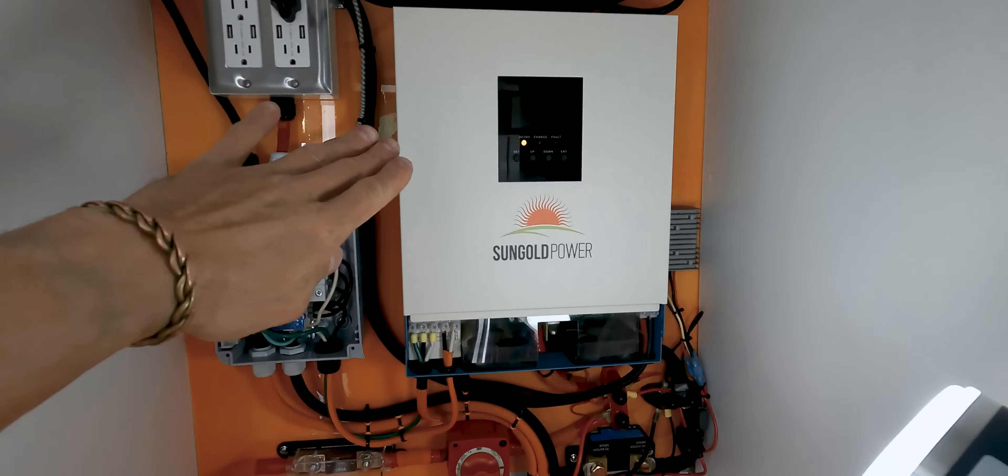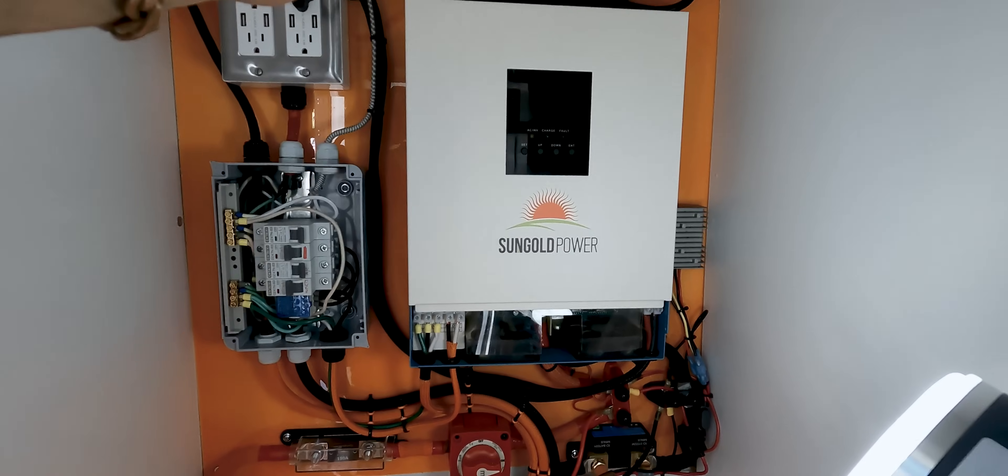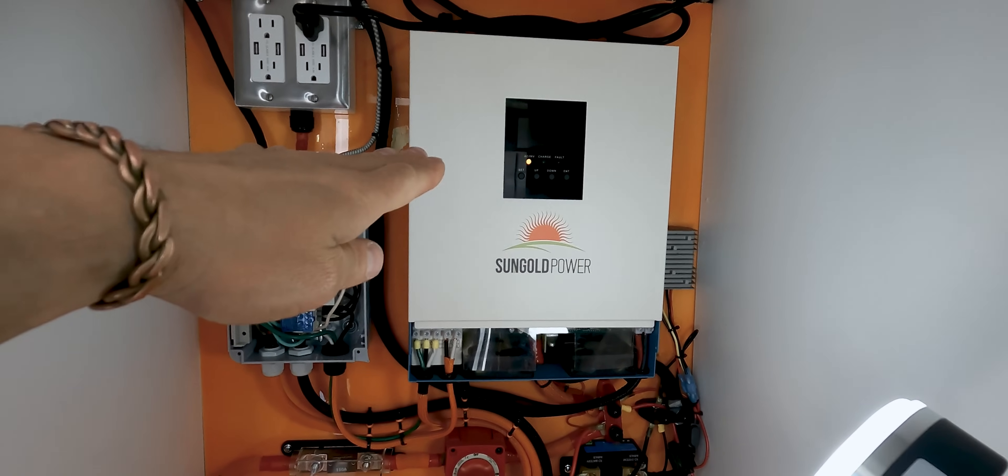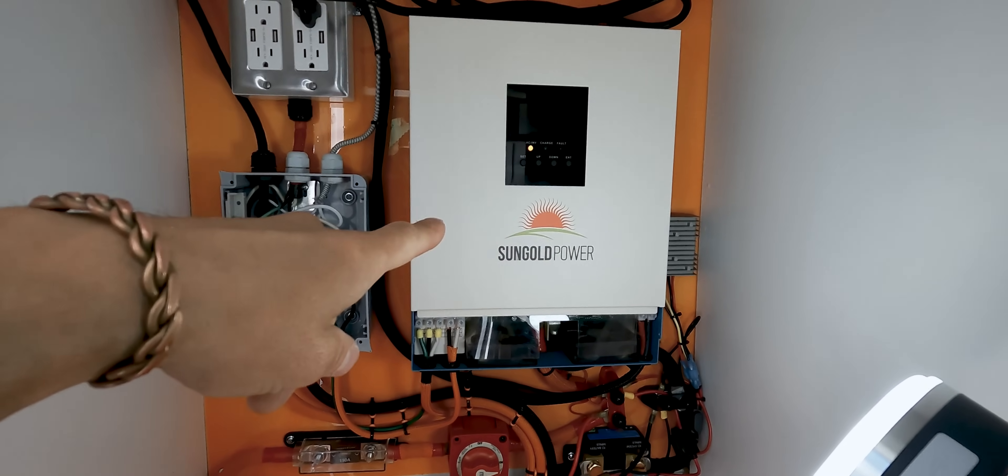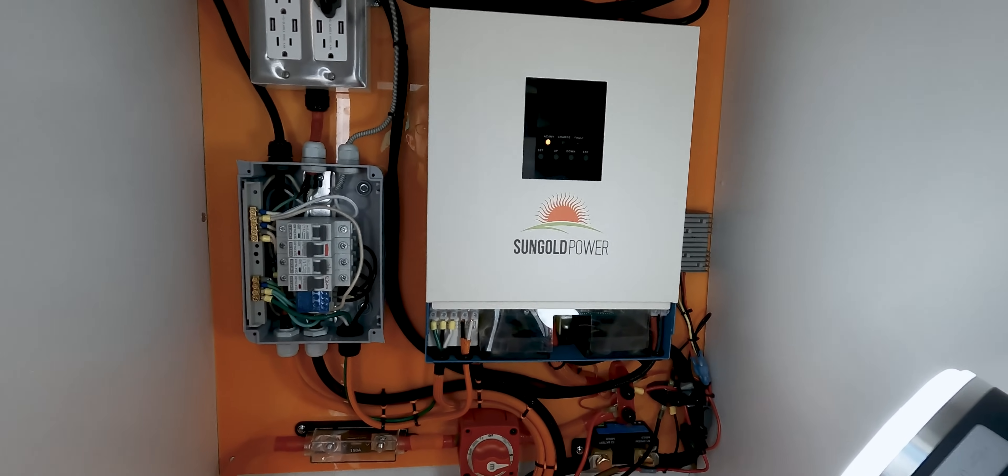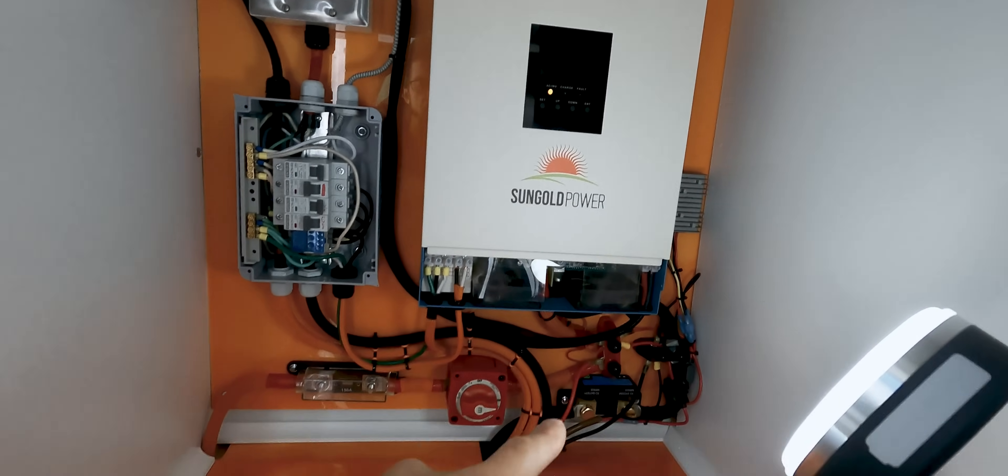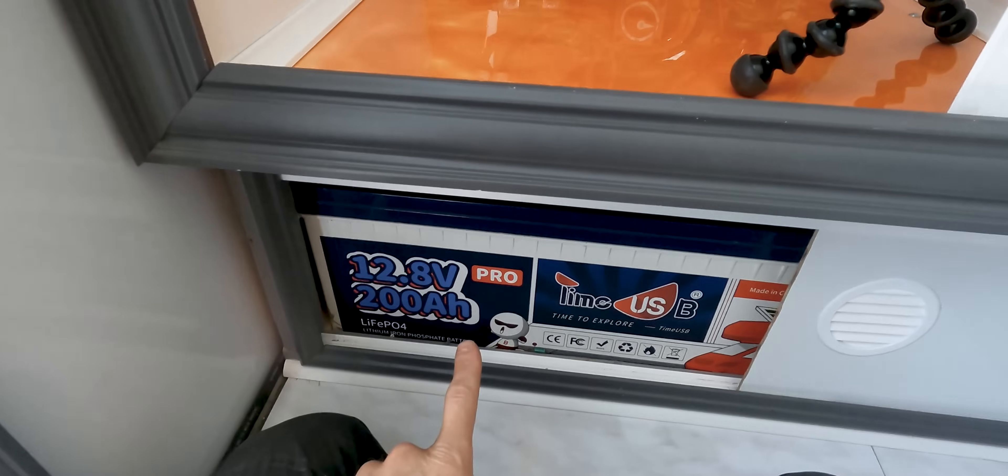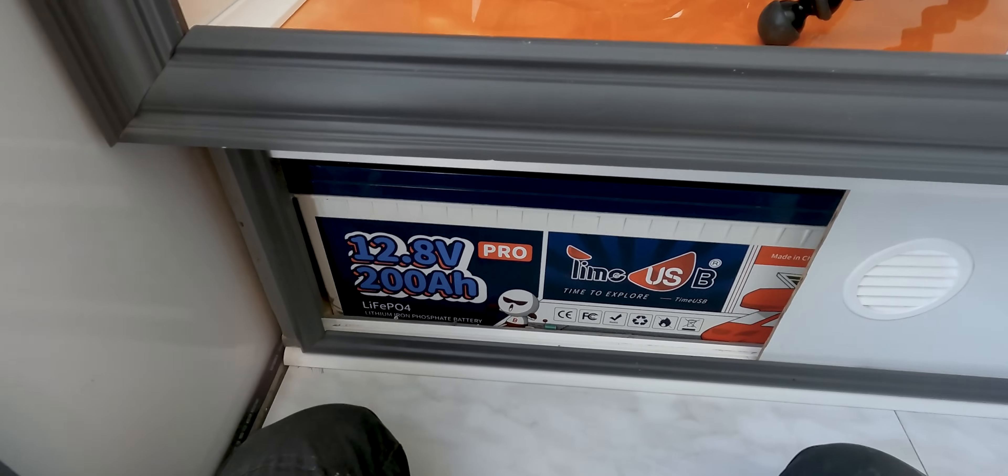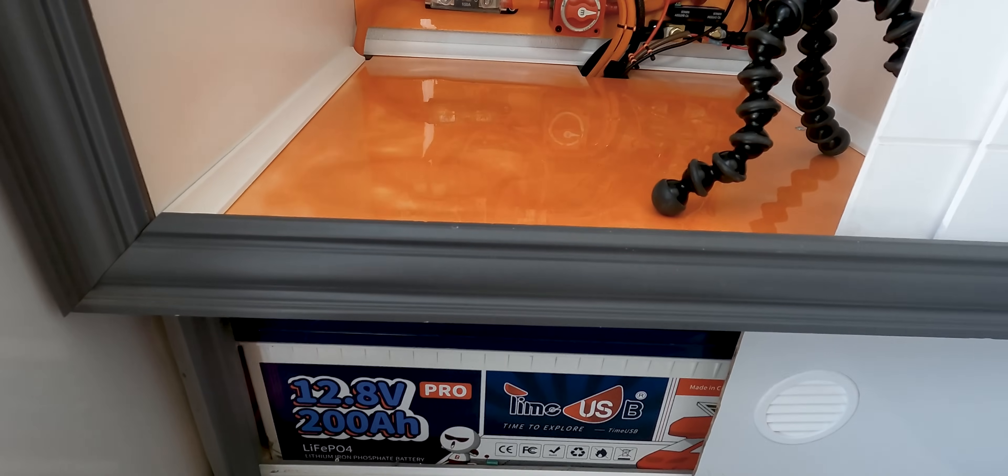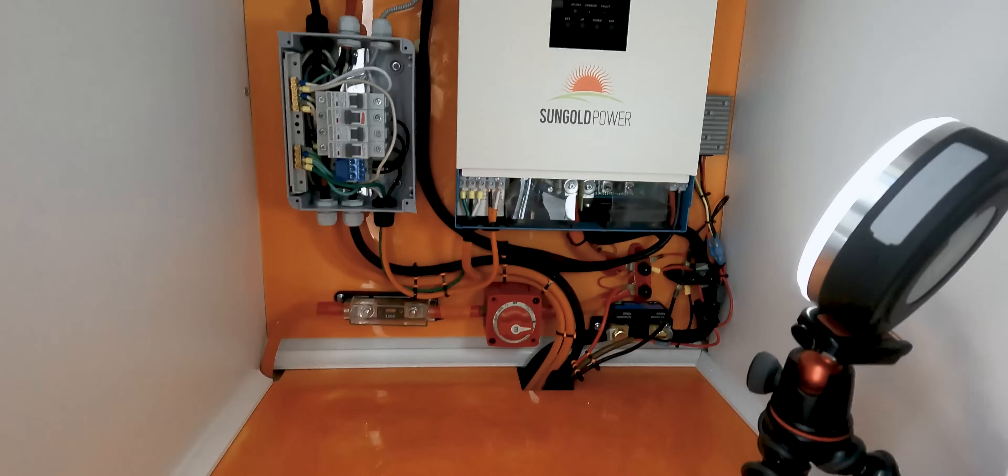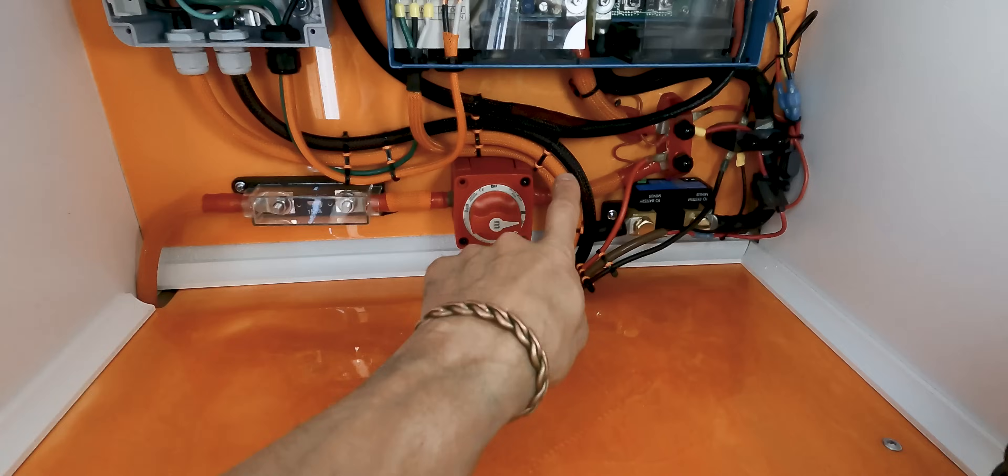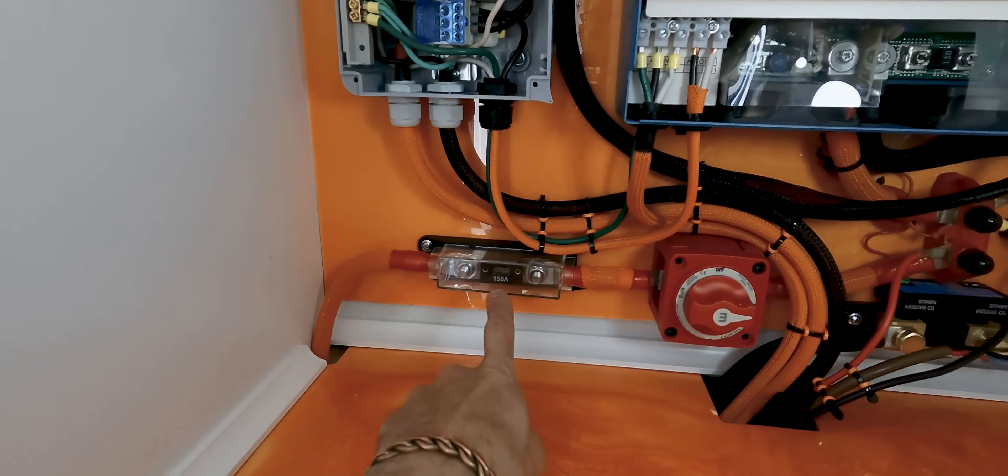So again, I have the all-in-one SunGold Power, 3000 watt inverter charger that brings in the solar power from my panels. It brings in the 110 volt shore power if I plug in outside. And additionally, it works as an inverter, so it's connected to my batteries, which are underneath this cabinet. I have two 12.8 volt, 200 amp hour Time USB batteries, two of them wired in series into a 24 volt battery bank. And so the way it works, I have all my cabling coming up out of the floor.